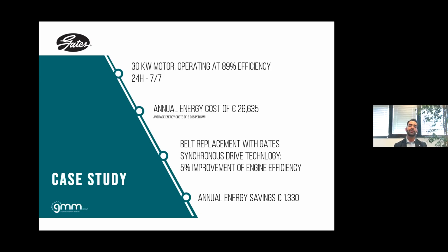For example, if we have a 30 kilowatt electrical motor operating at 89% efficiency, 24 hours a day, 7 days a week, about 11 months per year, we get an annual energy cost of 26,000 euros. When we replace the transmission element, in this case the belts, with, for example, Gates technology synchronous drive, we get an improvement in engine efficiency of about 5%, which translates into an annual energy saving of about 1,300 euros.